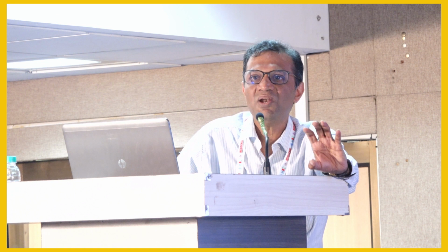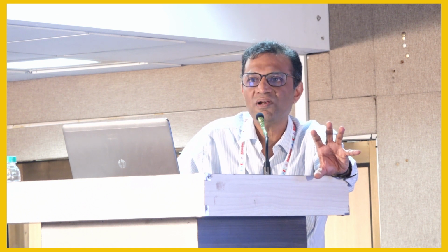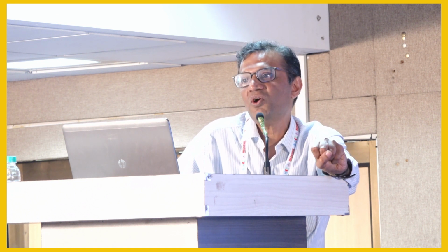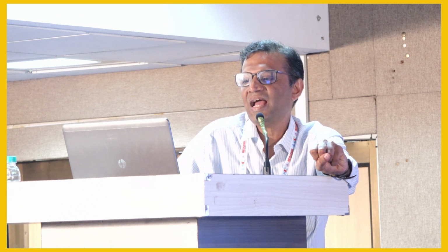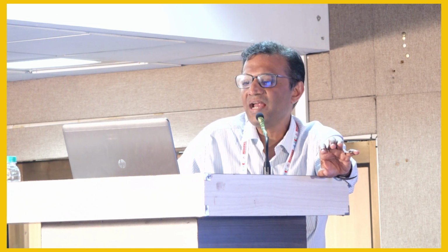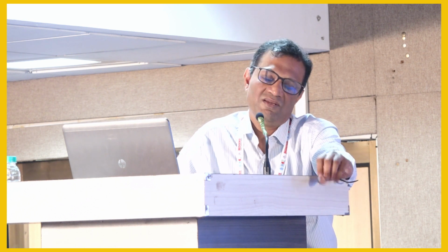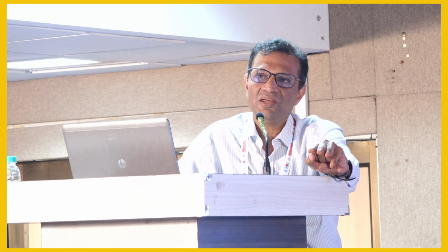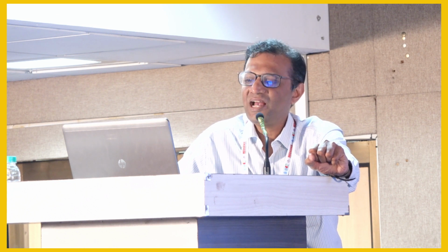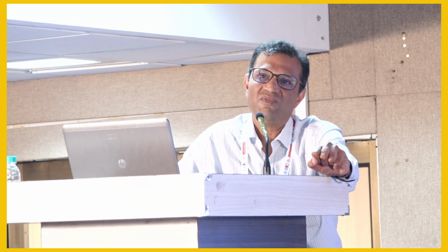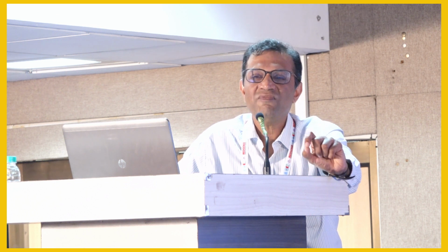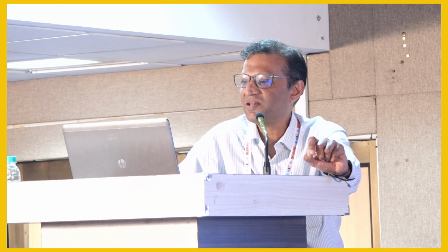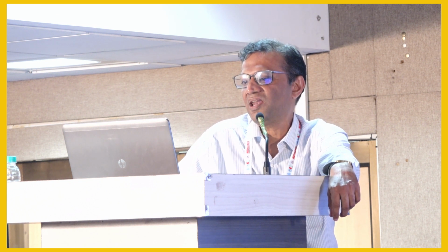If there are red blood cells, green and red are complementary colors. So, the RBCs will absorb some of the green light, and scatter the rest, so that the light reaching the photoelectric cell is attenuated, and this gives a blood leak alarm. Now, what was said this morning is that if you have a dirty chamber, you will have to clean that. So, if precipitates form on the photoelectric cell over here, they will obscure the light from reaching the photoelectric cell, and that will give a false blood leak alarm.